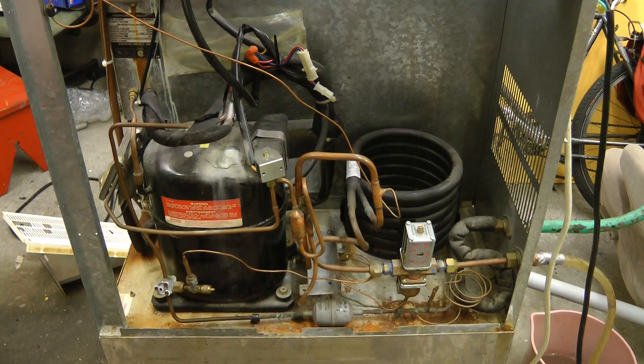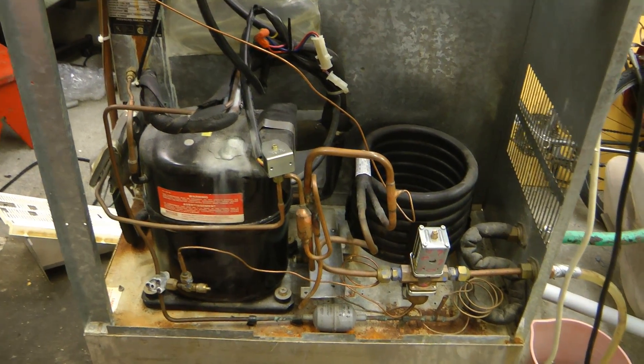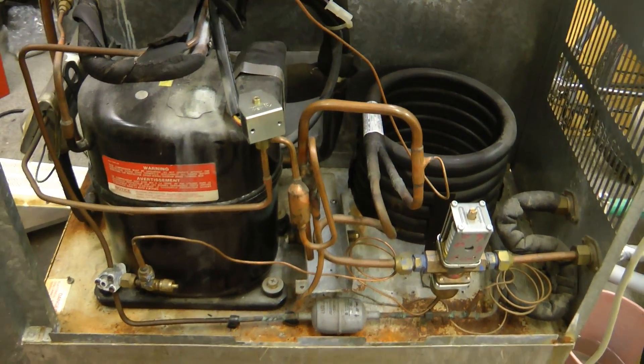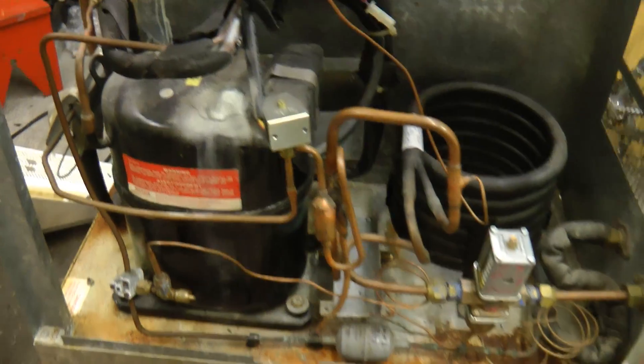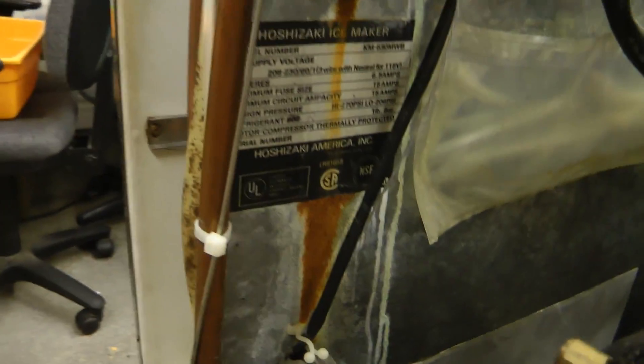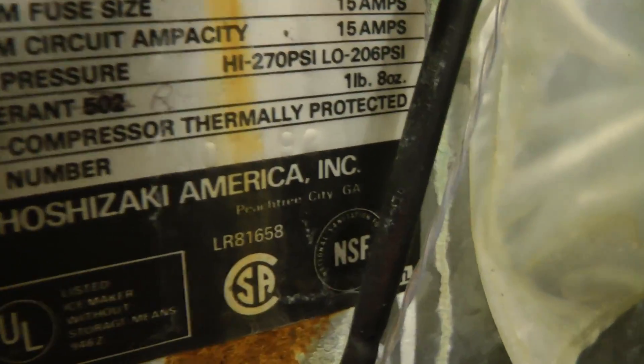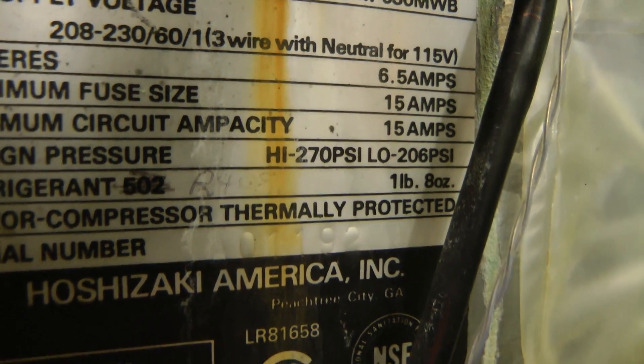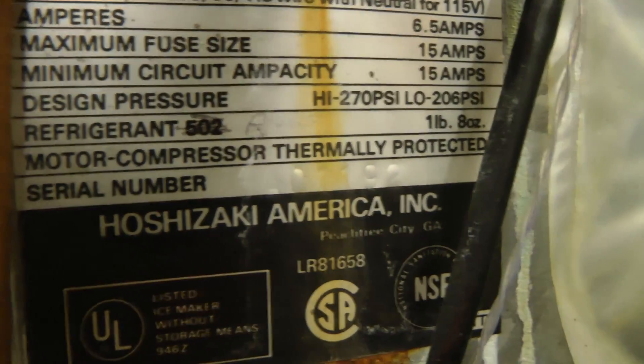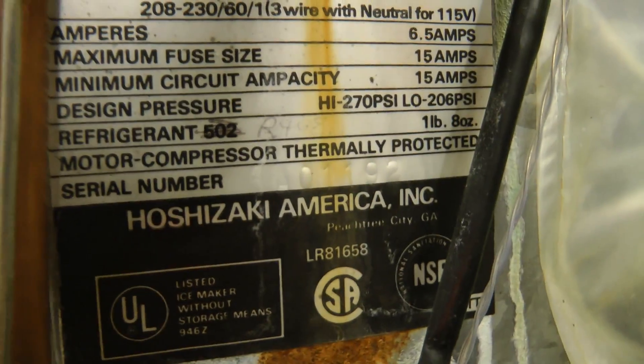The refrigeration system in this is reasonably typical although it doesn't use the normal R12 or R22 or any of the newer refrigerants, it uses R502, although the label here indicates it's been changed out for R408.